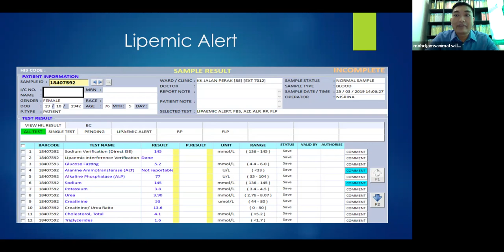And even the icteric alert, even though it is a patient condition and nothing much can be done, the result needs to be reported with an alarm. But it's also a good example that the icteric index can be used as a consistency check. Based on our study, the total bilirubin and icteric index have a very good correlation. So it can be used as a consistency check: if, let's say, there is a high bilirubin with a low A3, or a high A3 with a low bilirubin, there is something wrong with the analyzer. It can also be used as a decision for total bilirubin: for any sample sent to the lab without total bilirubin but with a very high icteric index, especially from the outpatient department, probably we need to add on total bilirubin, a liver function test, for further evaluation of the patient.